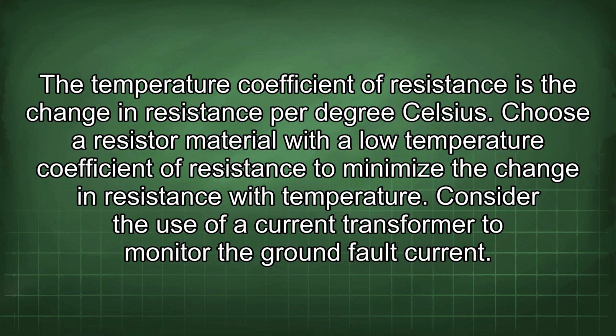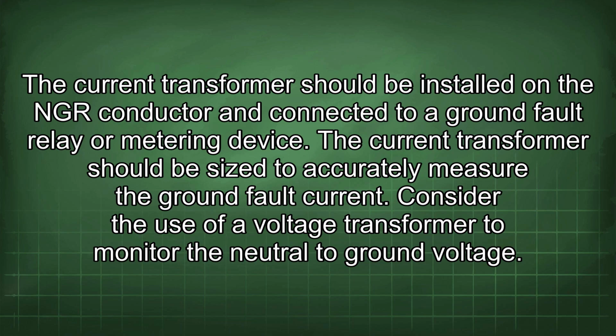Consider the use of a current transformer to monitor the ground fault current. The current transformer should be installed on the NGR conductor and connected to a ground fault relay or metering device. The current transformer should be sized to accurately measure the ground fault current.